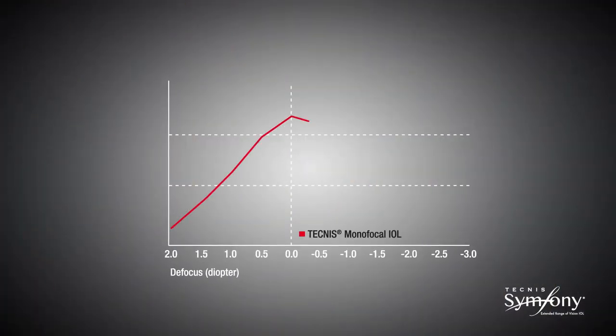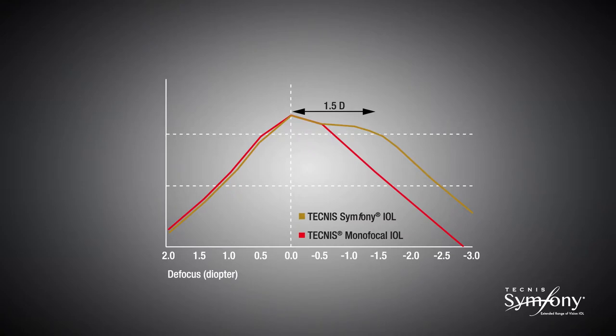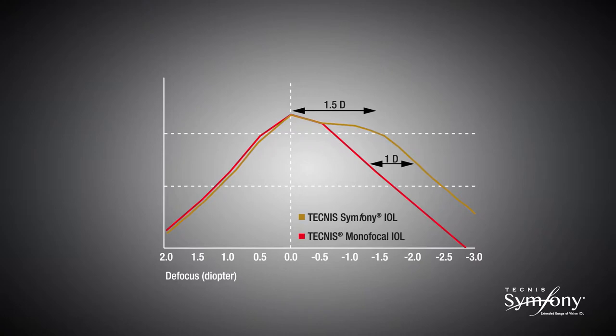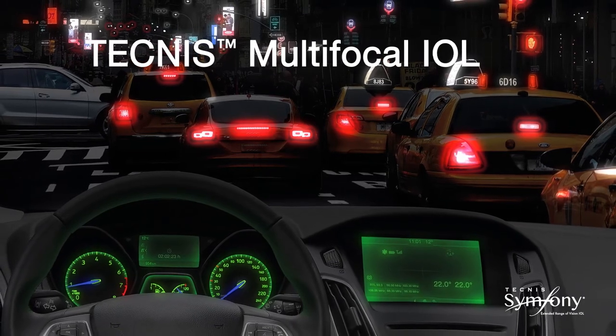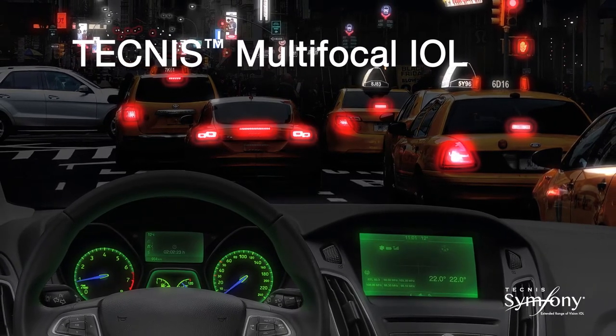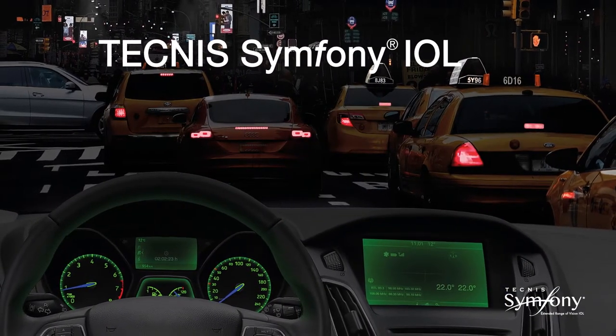Because of its elongated focus, the Technis Symphony IOL delivers high-quality vision through 1.5 diopters of defocus and an increase of 1 diopter range of vision throughout the defocus curve compared to a monofocal IOL. The plateau of the defocus curve demonstrates the extended range of vision of the Technis Symphony lens. In addition, because of the elongated focus, the Technis Symphony IOL does not have the distinct focal points of a multifocal IOL, and as such does not have the distinct out-of-focus images that can lead to halo and glare.